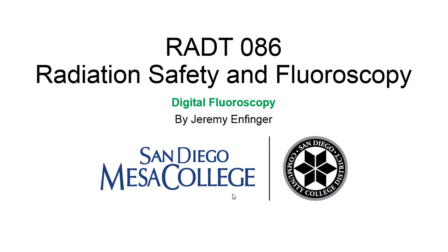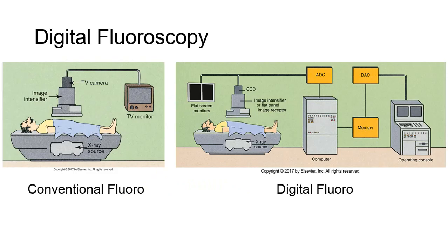Digital fluoroscopy — the introduction of digital fluoroscopy, where a computer has been added to traditional fluoroscopic equipment, has provided many advantages. A pulsed progressive mode has been added where the X-ray tube underneath the table can operate at an MA measured in the hundreds, like traditional X-ray overhead tubes, but using extremely short bursts of radiation with cooling periods between them. This is like an extreme version of pulsed fluoro mode, but it is not dependent upon the incoming current frequency to the X-ray generator.